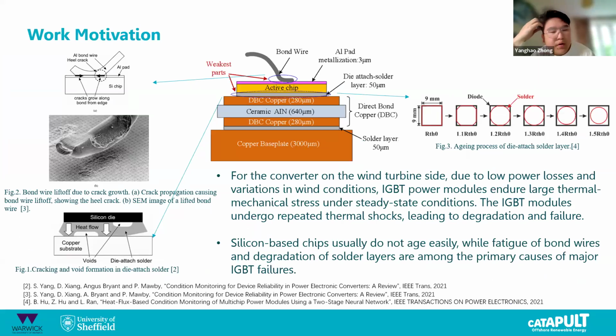IGBT modules in wind turbine converters face high thermal stress and repeated thermal shock, causing wear and failure. But the silicon chip or silicon combined chip doesn't age quickly, and bond wire cracking and solder layer wear are the main causes of IGBT failure. To describe the degradation of the device over time, the percentage change in the thermal resistance of the module is often used. The most direct impact of changes in it is the junction temperature of the chip. Therefore, it's important to monitor the condition of it.